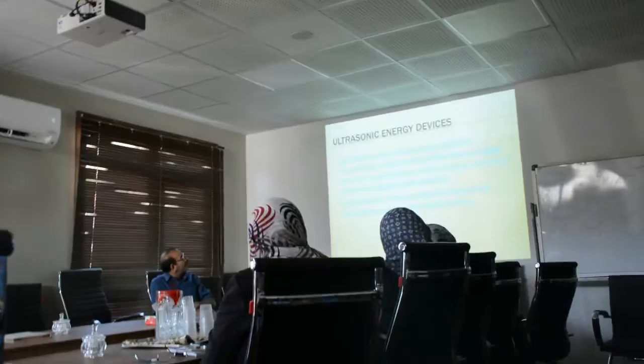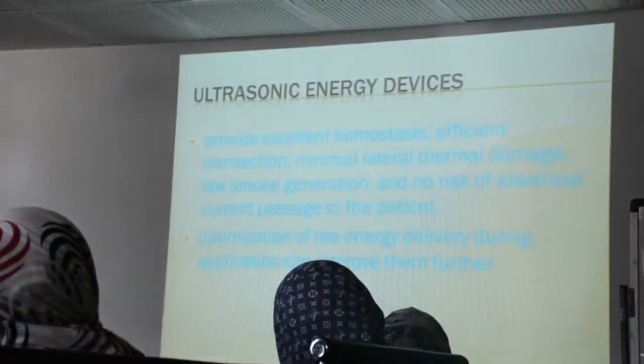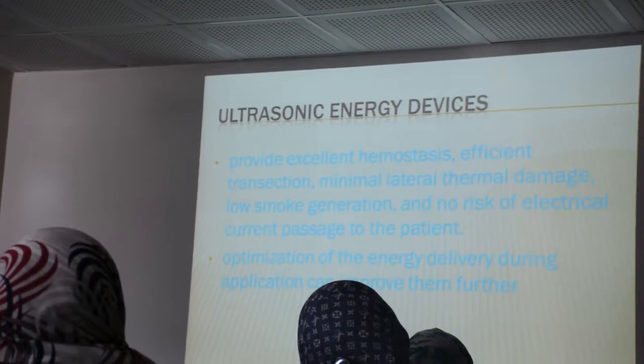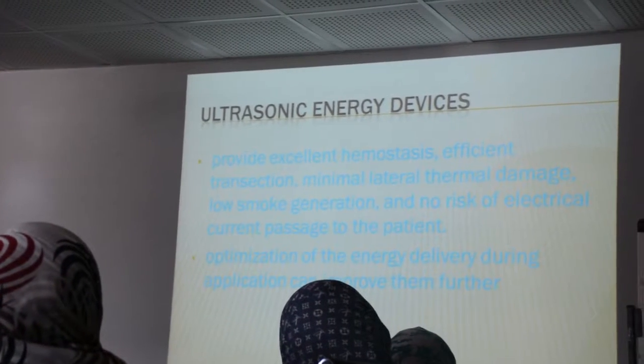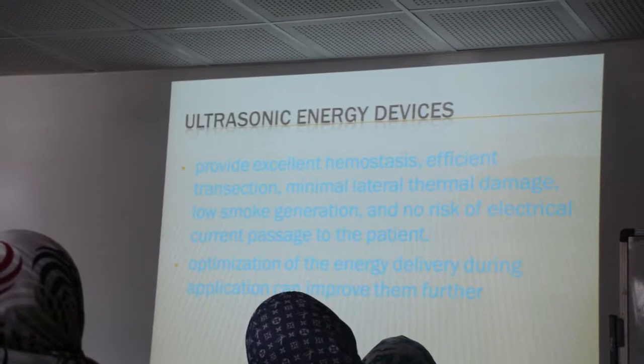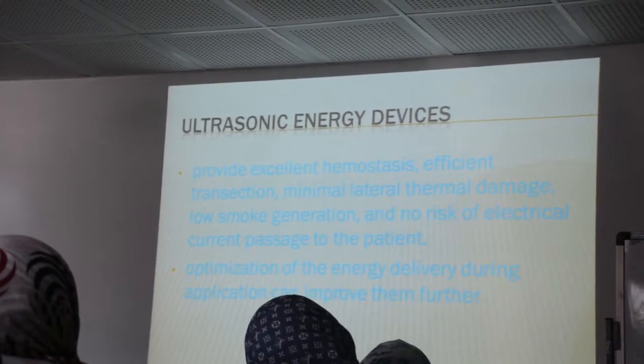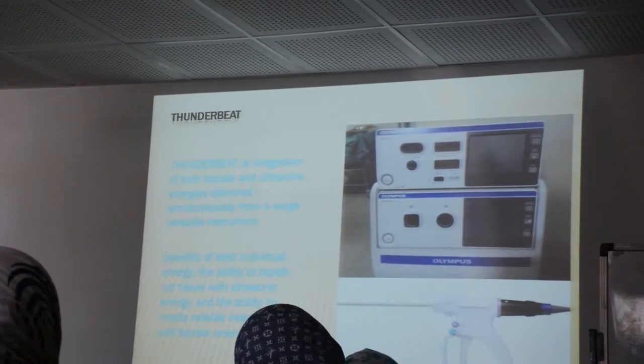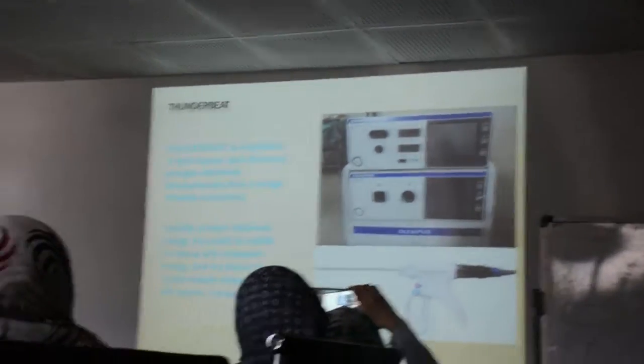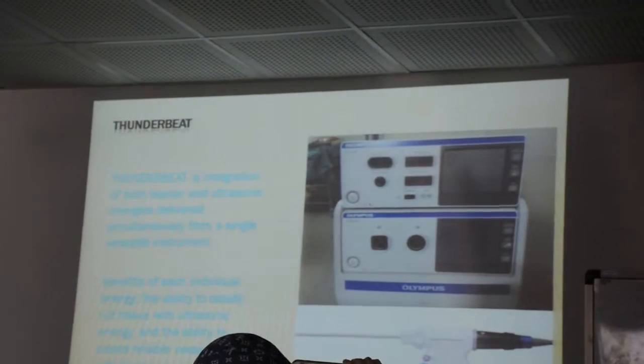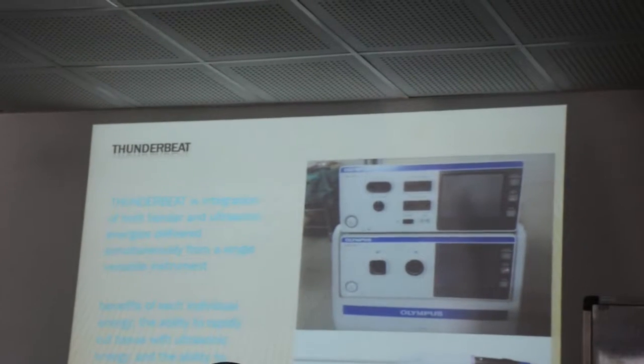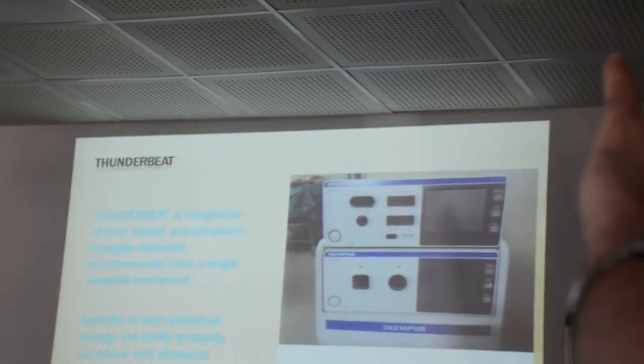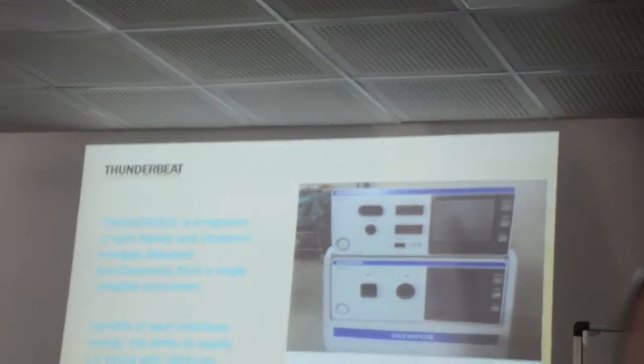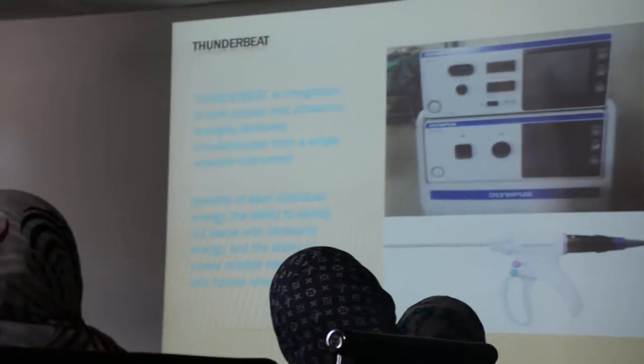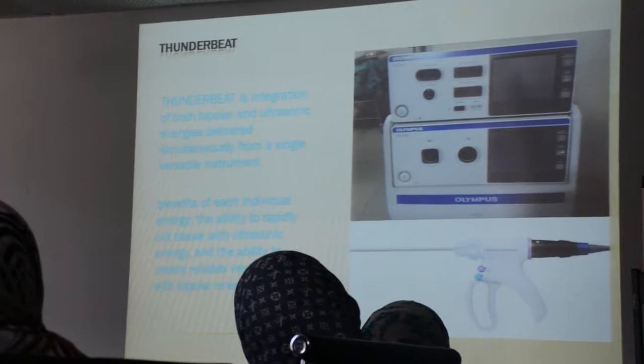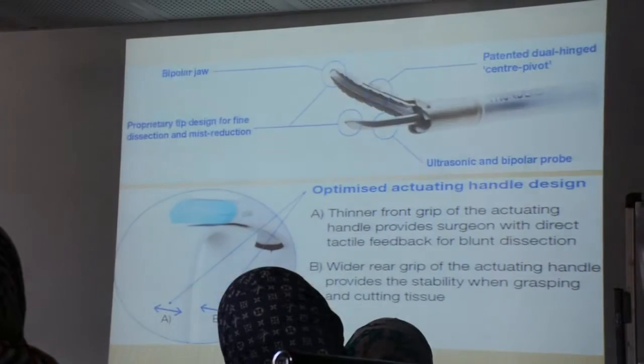Ultrasonic energy device provides excellent hemostasis, efficient transection, minimal lateral thermal damage, low smoke generation, and no risk of electrical current passage to the patient. Optimization of the energy delivery during application can improve them further. Thunderbeat is the integration of both bipolar and ultrasonic energies delivered simultaneously from a single versatile instrument. Benefits of each individual energy: the ability to rapidly cut tissue with ultrasonic energy and the ability to create a reliable vessel seal with bipolar energy.